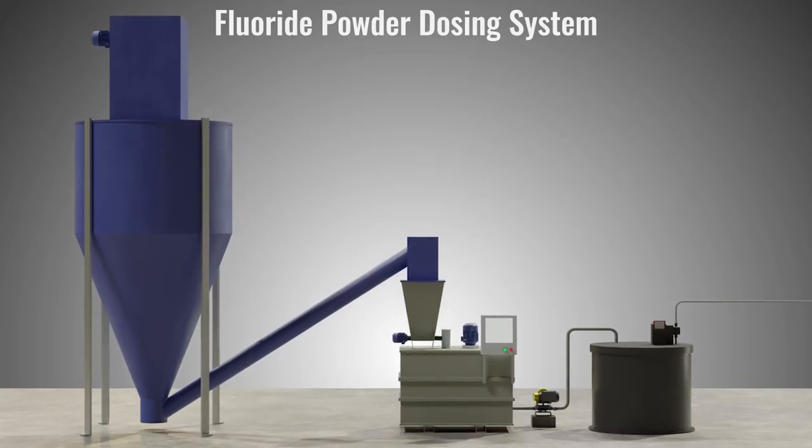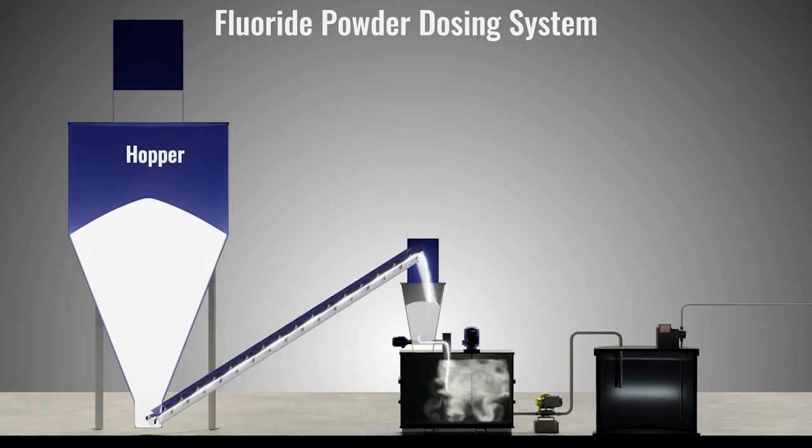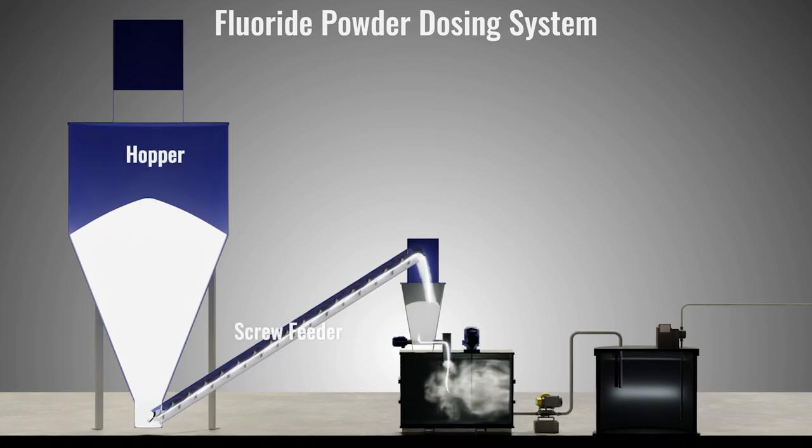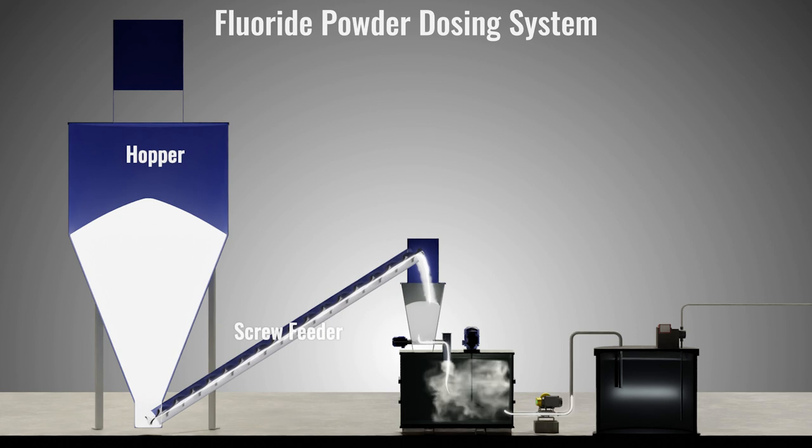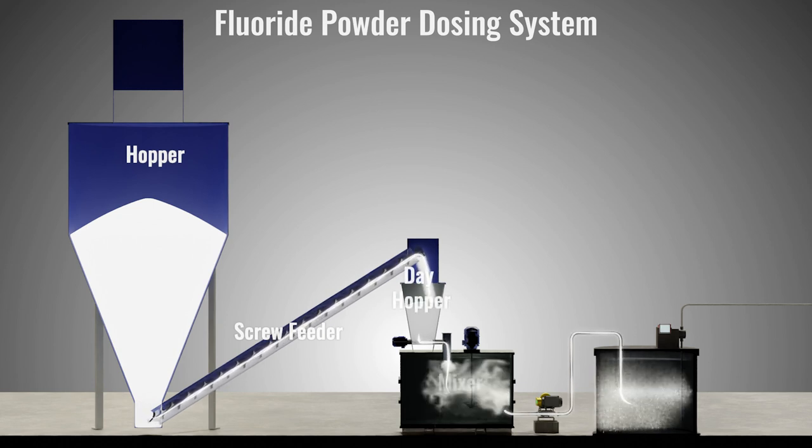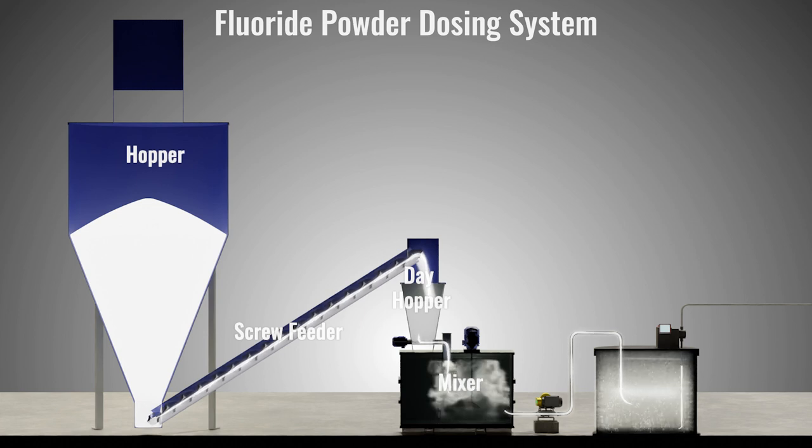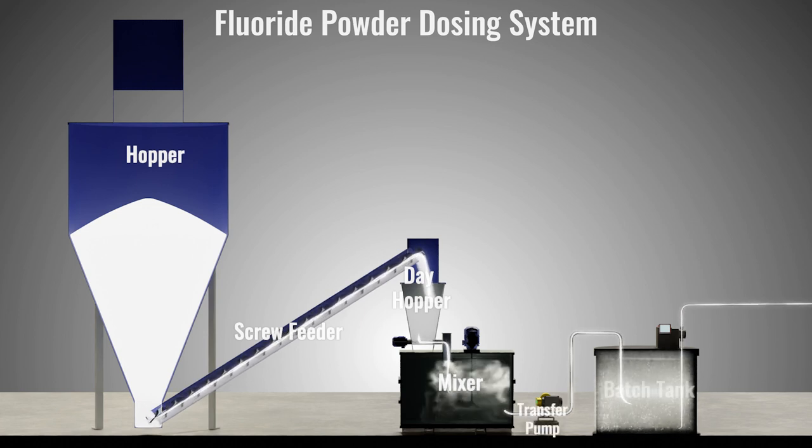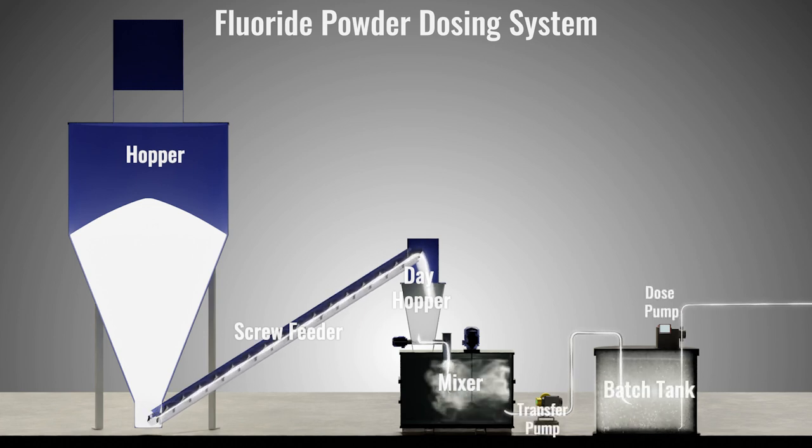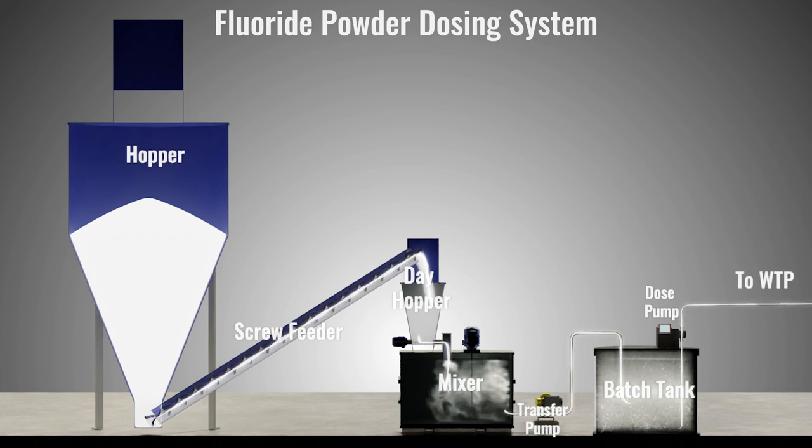There's also a liquid form which is hydrofluorosilicic acid, and that's a liquid which is dosed into the water. With the powder forms, they are usually dosed with a hopper using a screw feeder to deliver a measured mass of the powder into a mix, essentially with a liquid.